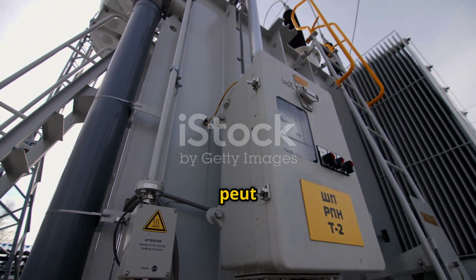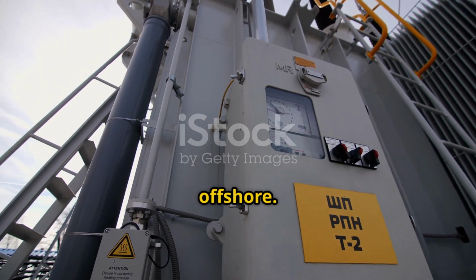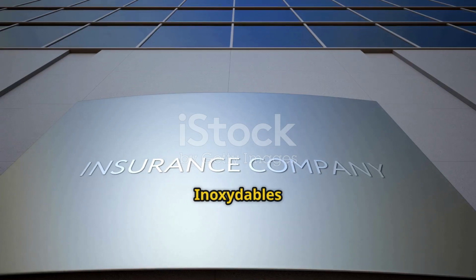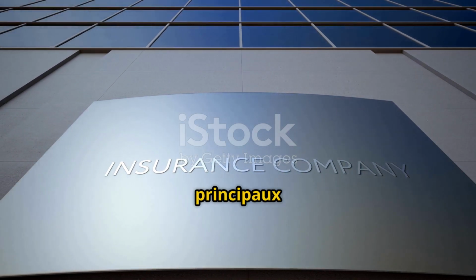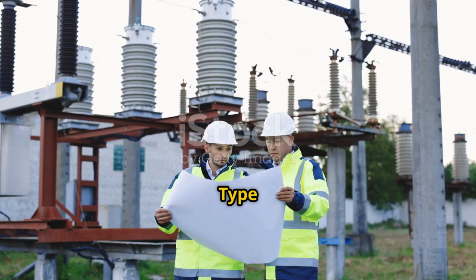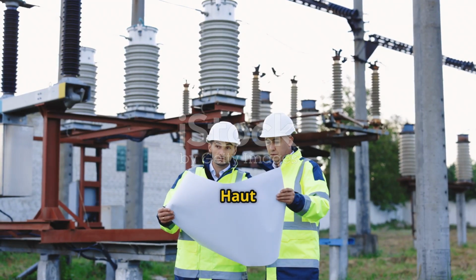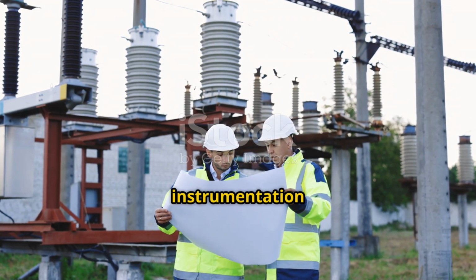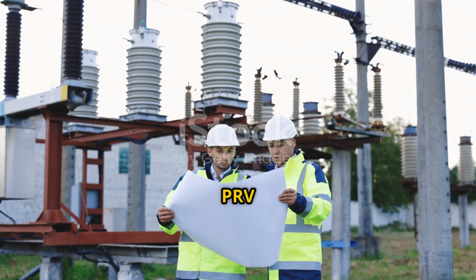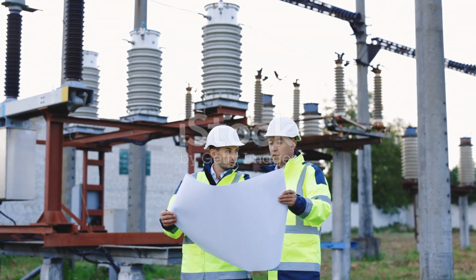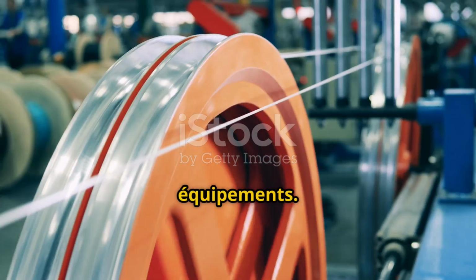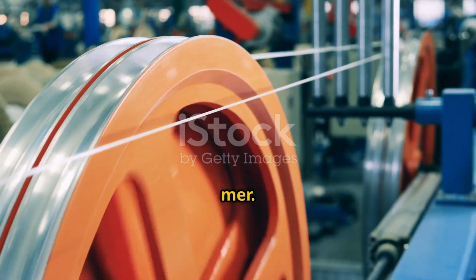Beyond the legally mandated electrical codes, like the NEC and the CEC, there is another layer of standardization that plays a crucial role in the industry: the standards published by trade associations, most notably the National Electrical Manufacturers Association, or NEMA, in the United States. NEMA's standards are not law, but they are created by the manufacturers themselves to establish a baseline for product performance, construction, and classification. These unwritten rules are so widely adopted that they have become a de facto requirement for doing business. Specifying a NEMA 12A rated tray, for example, is a shorthand that every engineer and supplier in the industry understands.